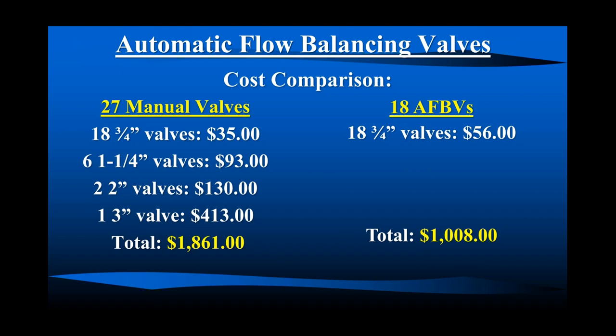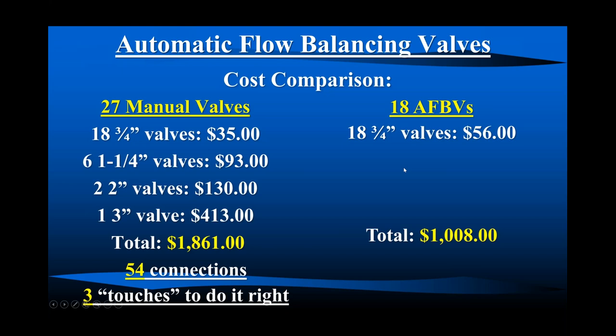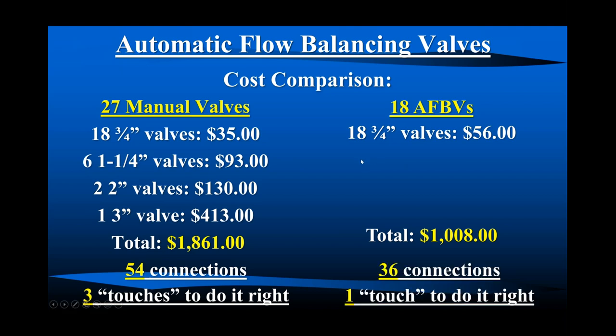So if we can explain this, automatic flow balancing valves are not more expensive than a well-designed manual valve system. It's 54 connections. And really, to do it right, you have to touch each manual valve 3 times, compared to 36 connections. And it's really 1 verification touch. It's automatic. You don't have to adjust it. Any questions on that? That kind of gets lost in the sauce on a lot of projects.